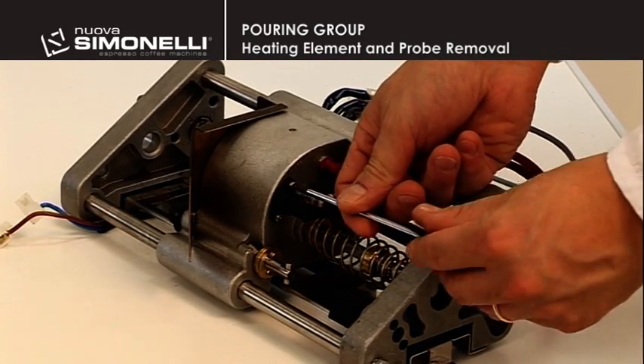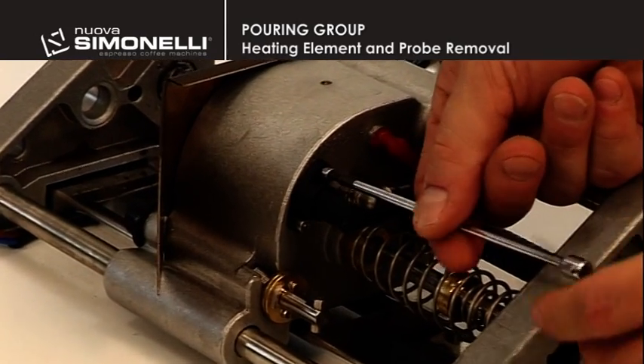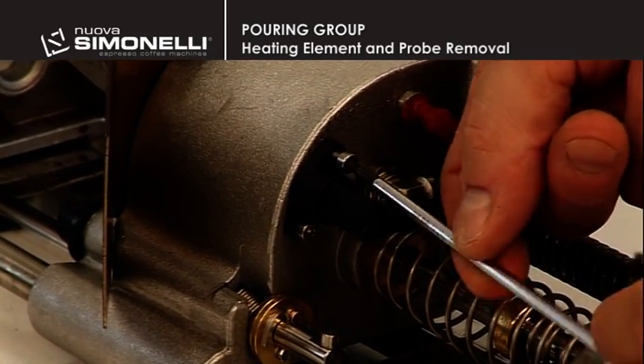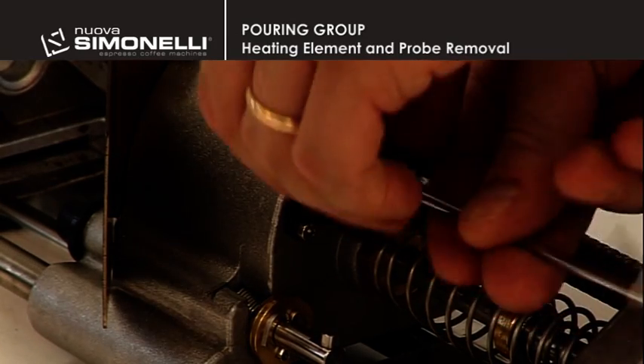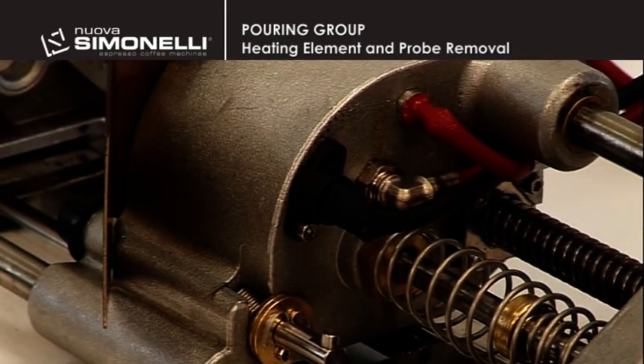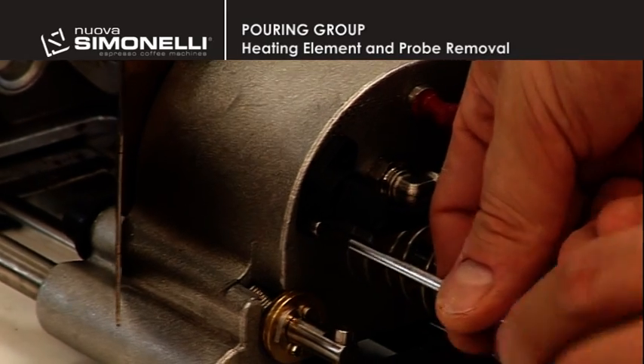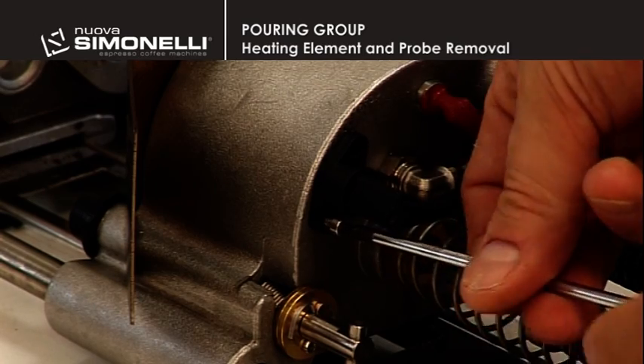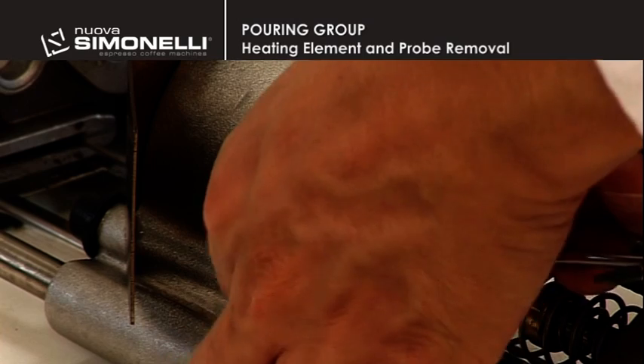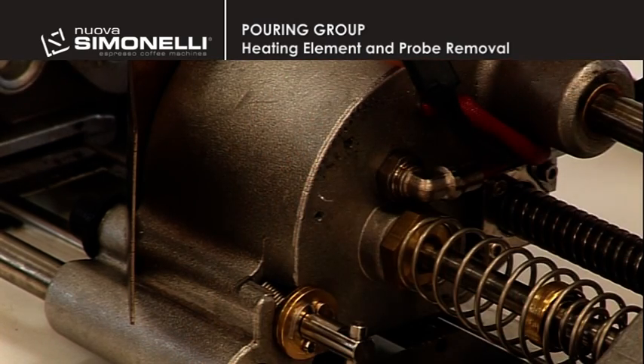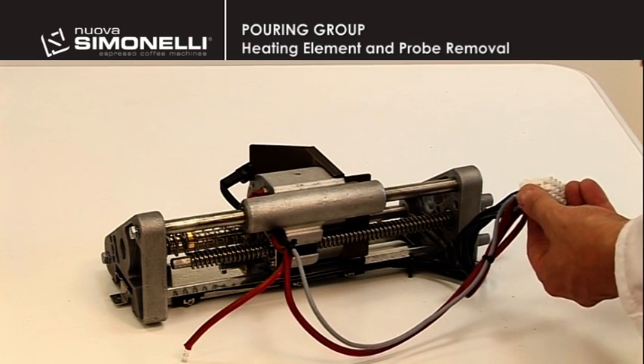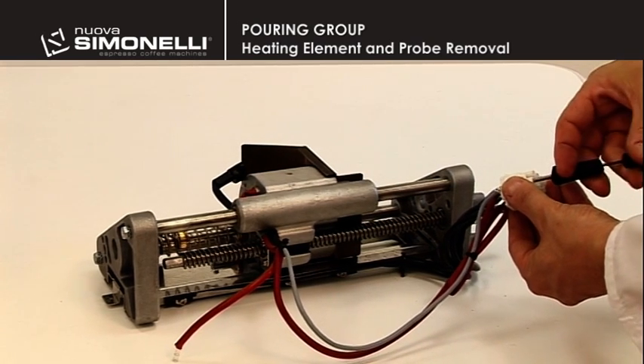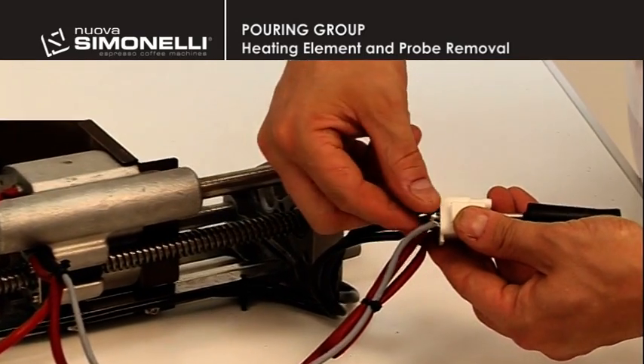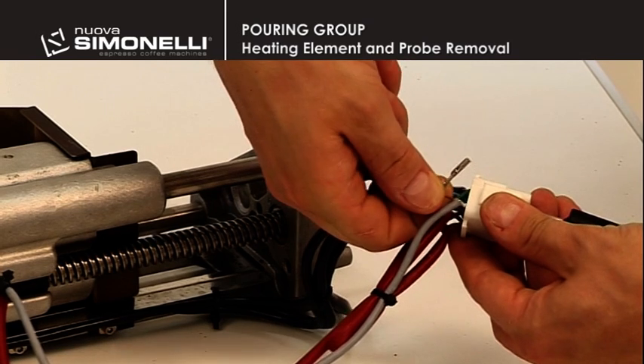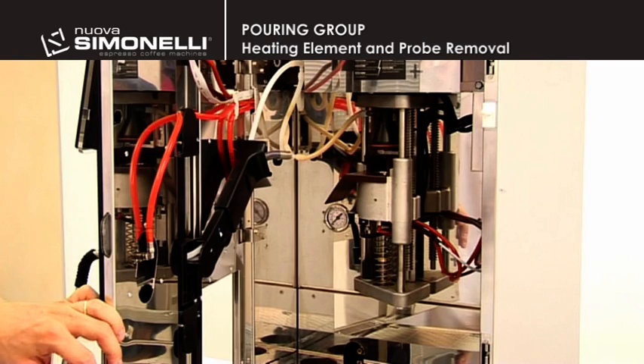The temperature probe is located at the base of the infusion chamber. Use a 2.5mm Allen wrench to remove the two screws. Then free the wiring from the clamps and disconnect the two pins from the wiring connector. This operation is possible with the group fitted on the machine, following the same procedure.